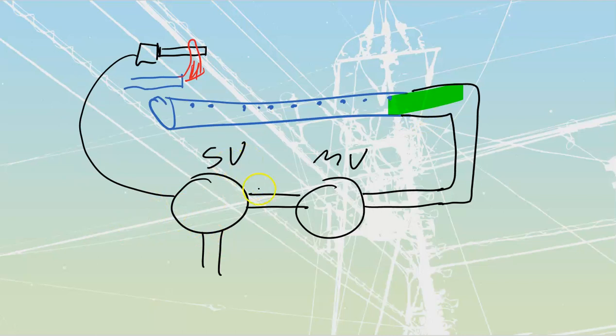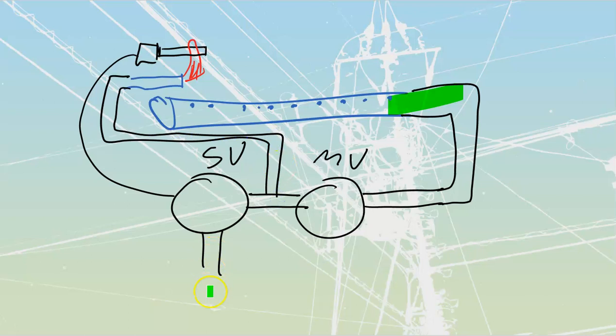If we have, and we're just going to take this one over here, line's got to go up there as well. So this is what we normally are going to have coming into here. We have gas that will make it through the safety valve. Past the safety valve, we will tap off, and we will run a small amount of gas up here to my pilot device. Whatever the pilot device is, it is going to run continuously.